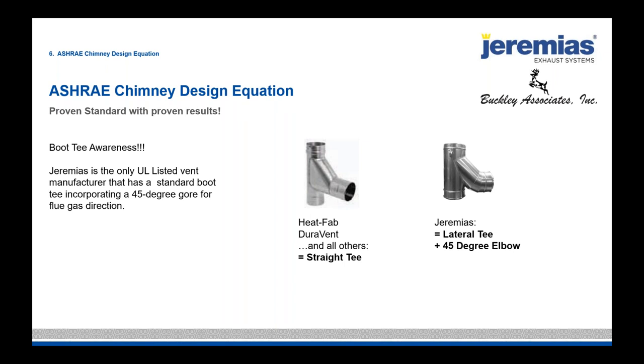It's important to know what type of fittings you're using — we call this boot tee awareness. Some manufacturers like Heat Fab and Duravent have a 90-degree boot tee with resistance like a 90-degree straight tee. Others like Jeremias have boot tees that are a combination of a 45-degree elbow and a lateral tee. On one side you use a 45-degree elbow to size, and on the other side a lateral tee — much less resistance, almost half. It's critical to know which manufacturer's fittings you're using.